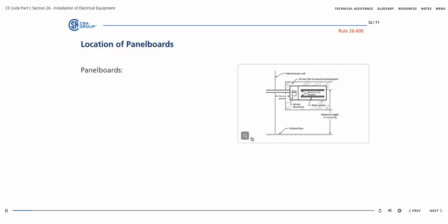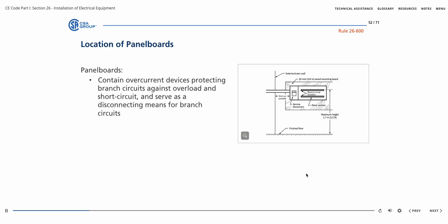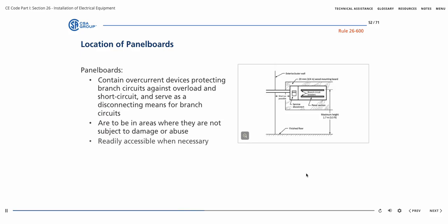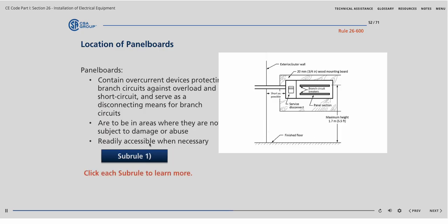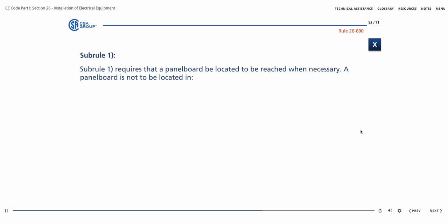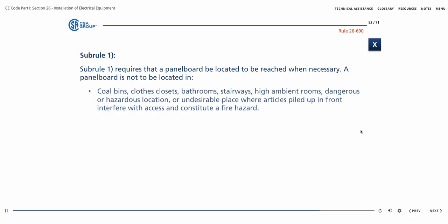The location of panel boards is important due to safety considerations. Rule 26-600 requires panel boards to contain overcurrent devices protecting branch circuits against overload and short circuit, and serve as a disconnecting means for branch circuits. They are to be in areas where they are not subject to damage or abuse, and are readily accessible when necessary. Sub-Rule 1 requires that a panel board be located to be reached when necessary. A panel board is not to be located in coal bins, clothes closets, bathrooms, stairways, high ambient rooms, dangerous or hazardous locations, or undesirable places where articles piled up in front interfere with access and constitute a fire hazard.